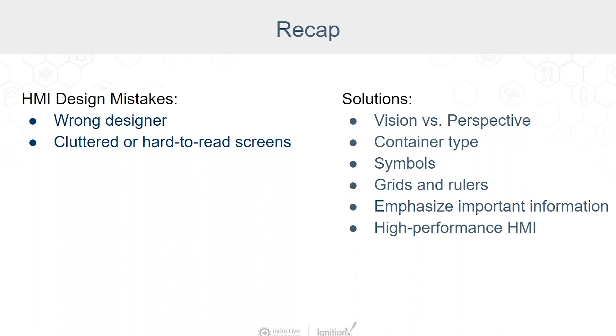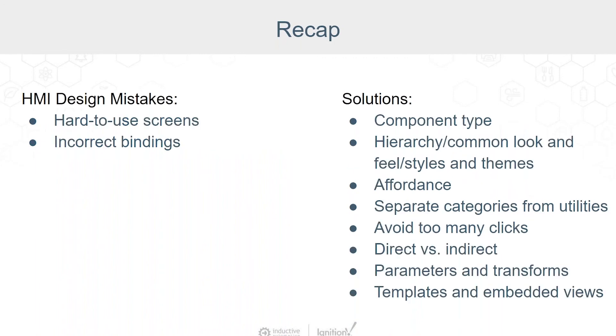To recap, some common HMI design mistakes are choosing the wrong visualization module — choosing between Vision or Perspective — and having cluttered or hard-to-read screens. Make sure you're thinking about that before you start building. Choose the right container type, use symbols, grids and rulers, and emphasize important information with color, position, size, isolation, and contrast. Incorporate a high-performance HMI philosophy. Other common mistakes are hard-to-use screens and incorrect bindings. The fixes are choosing the best component type, maintaining a consistent hierarchy, a common look and feel, and using styles and themes. Think in terms of clicks — consider affordance and separate categories from utilities. For bindings, think about whether you need direct or indirect, and use parameters, transforms, templates, and embedded views.